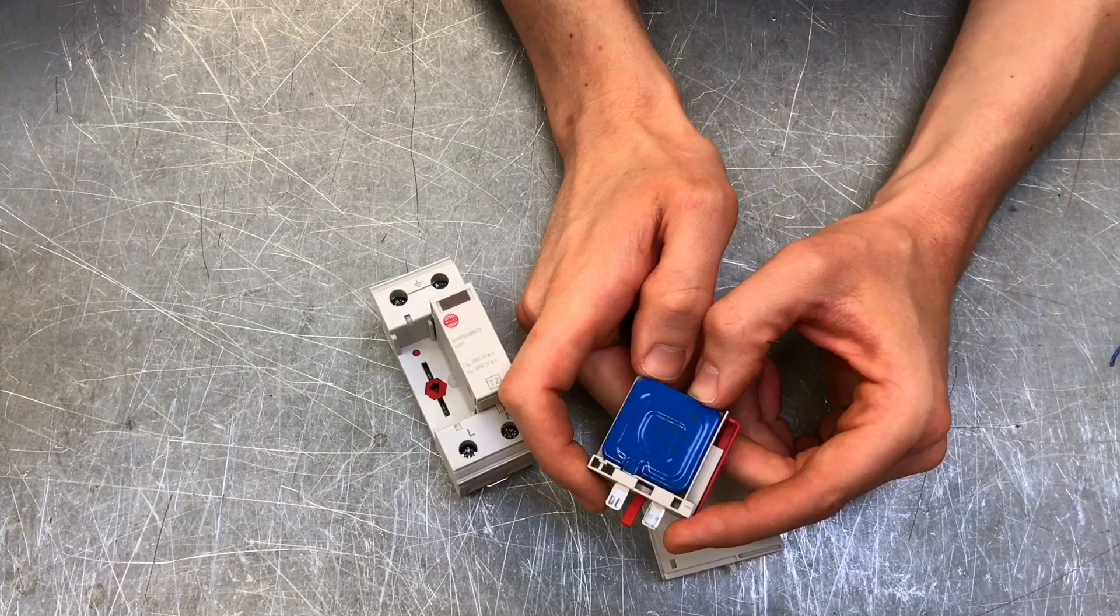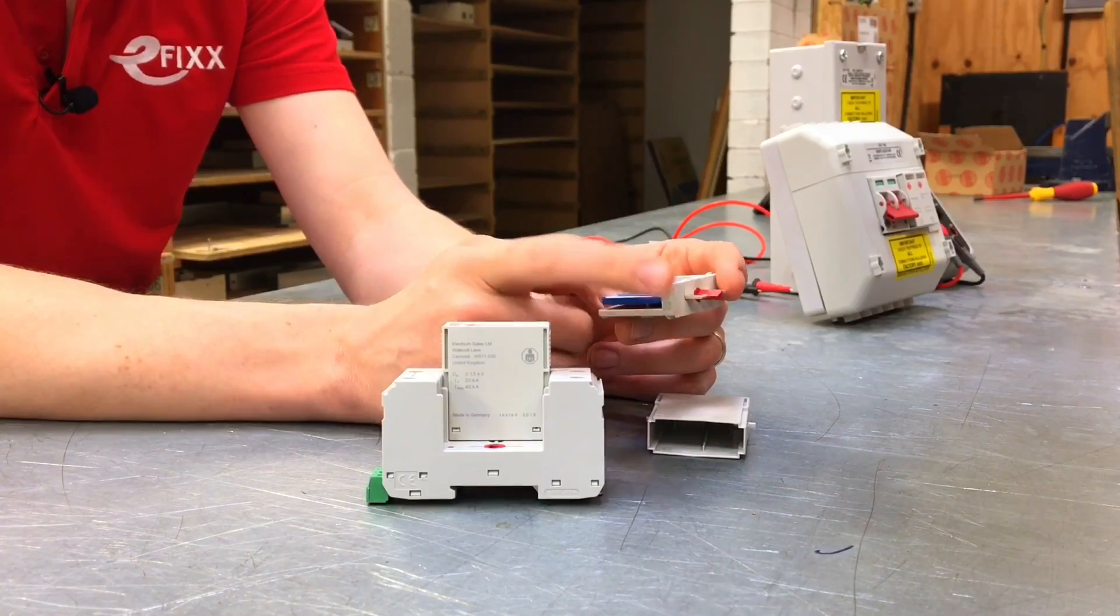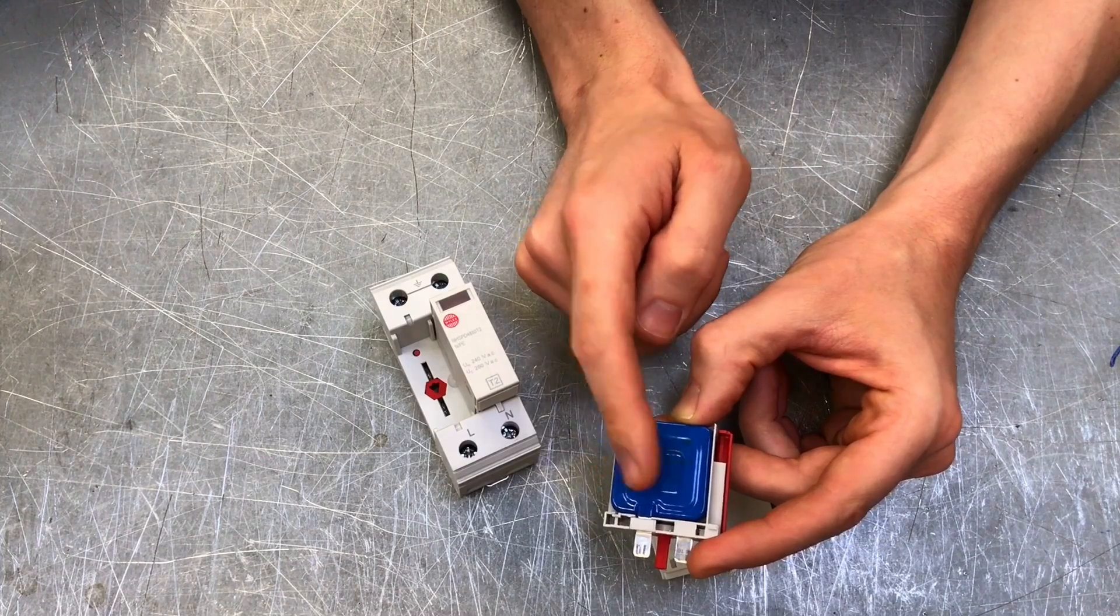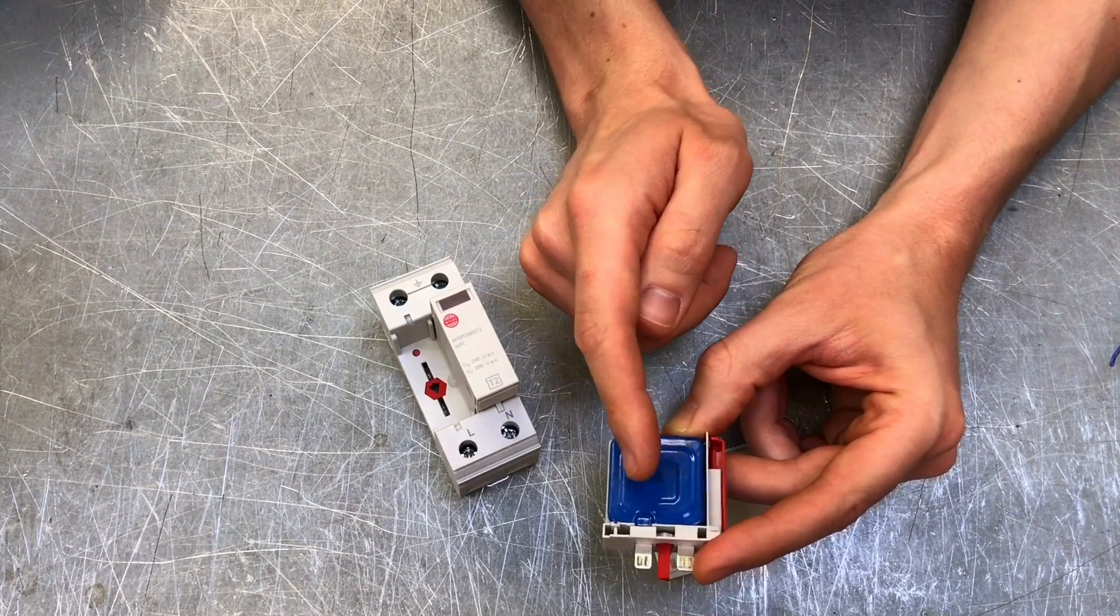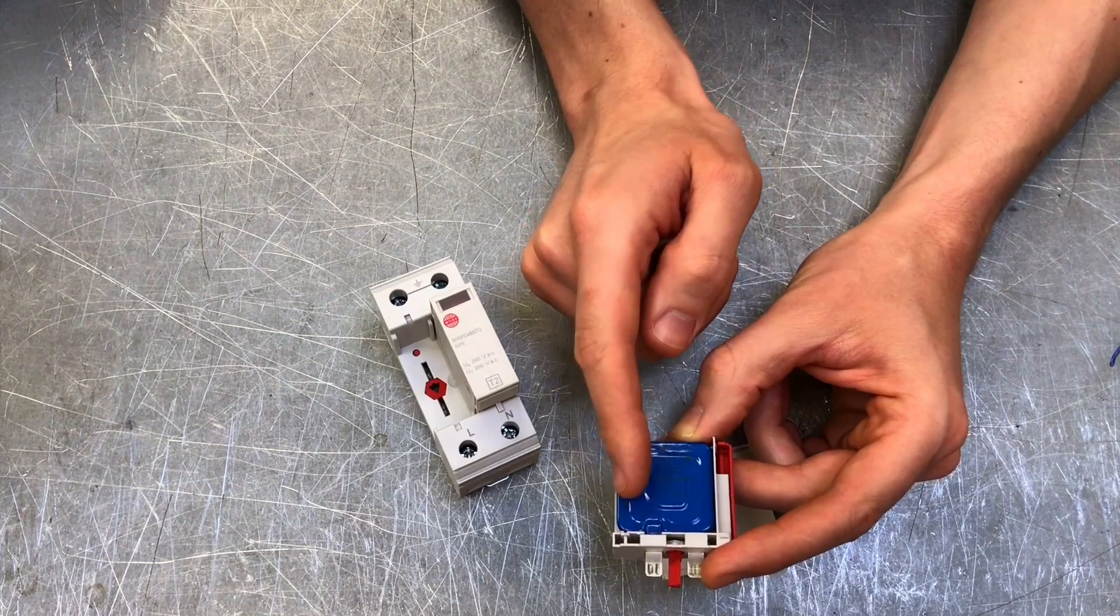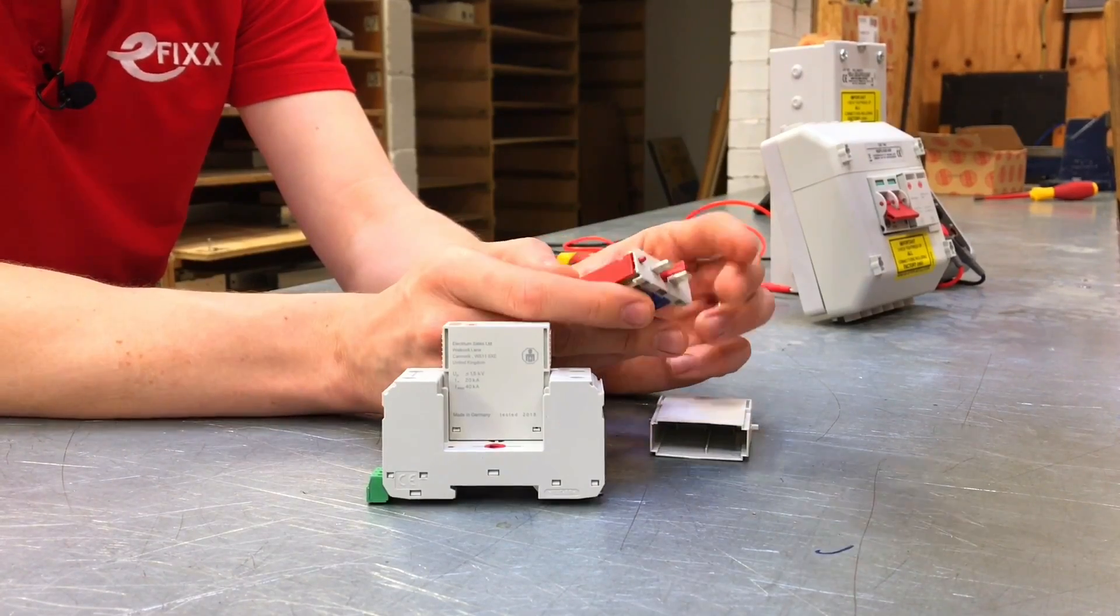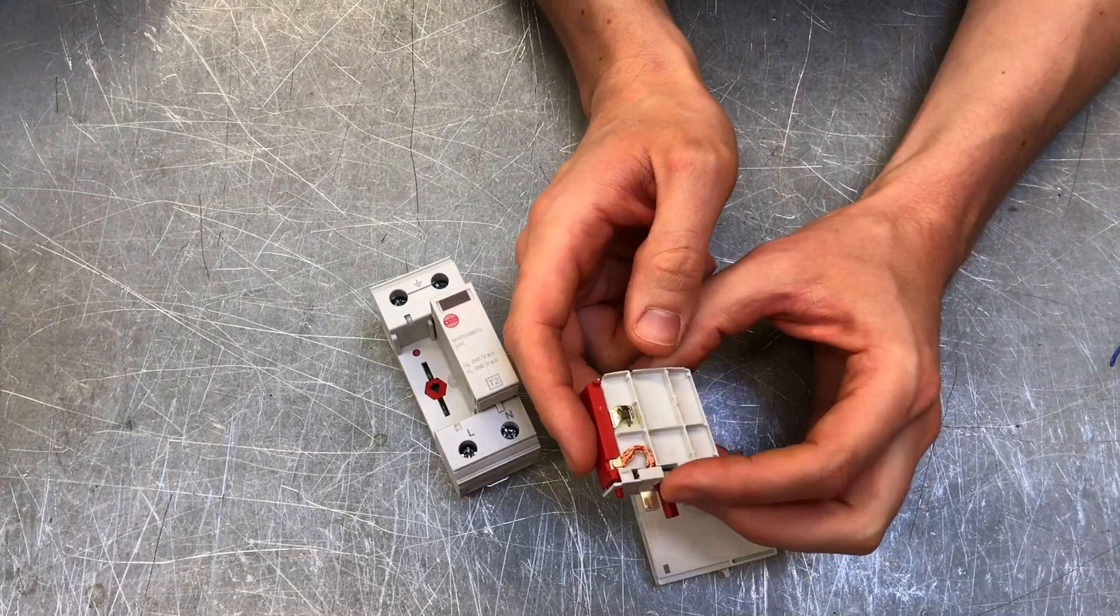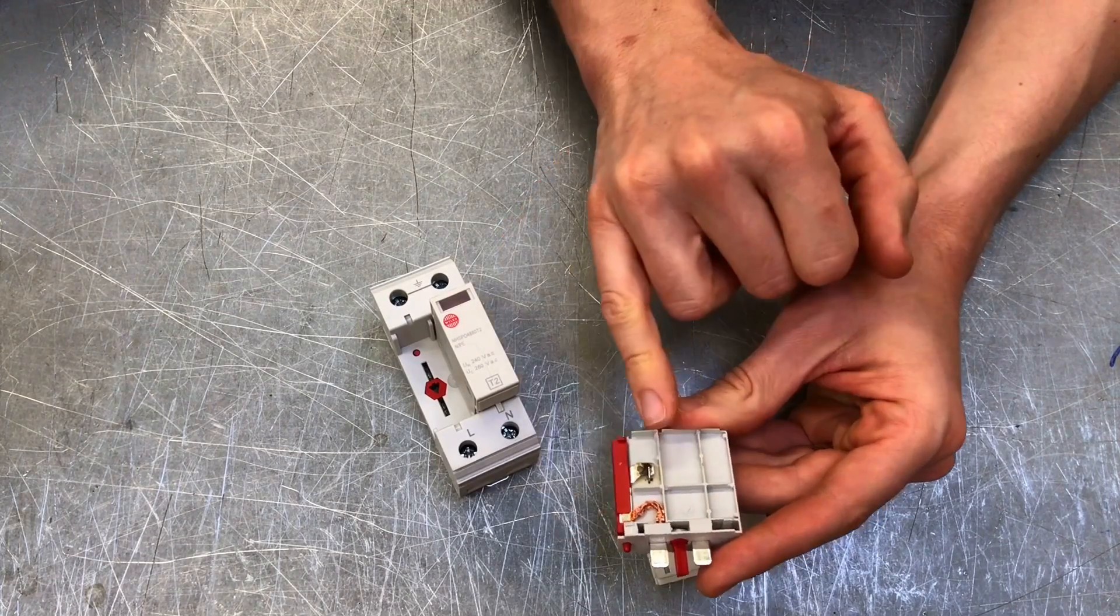When the varistor's life has elapsed, what happens to indicate this? These have an operational life. There'll come a point where its resistance won't drop down anymore after it's taken a number of shots from higher voltages. Because this is connected between line and earth, there's no way we could tell just by circuit operation that it had reached end of life. The circuit will continue to function perfectly happily until there's a huge transient voltage, and if this has gone past its operational life, it simply won't work and will be worse than useless because we think we've got protection when we don't.